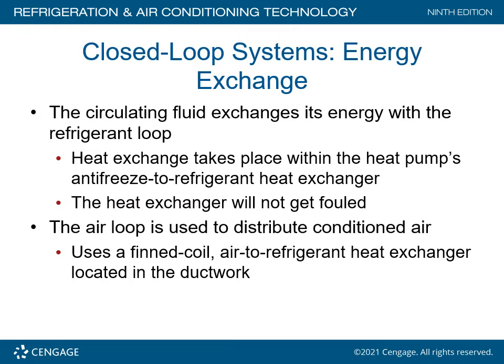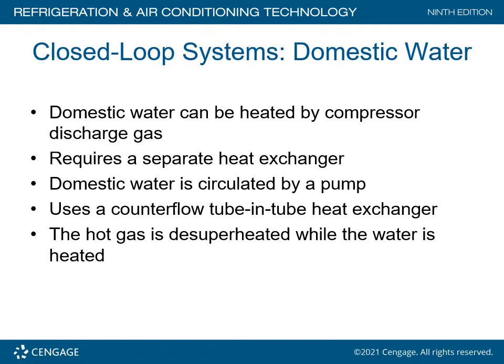In closed loop systems, energy exchange occurs when the circulating fluid exchanges energy with the refrigerant loop through an antifreeze-to-refrigerant heat exchanger inside the heat pump. The heat exchanger cannot get fouled because it uses treated water. The air loop distributes conditioned air using a fin coil air-to-refrigerant heat exchanger. Domestic water can also be heated by compressor discharge gas, requiring a separate heat exchanger with a circulating pump, utilizing a counterflow tube-within-a-tube heat exchanger. The fluids flow in opposite directions for maximum heat transfer, and the hot gas is de-superheated while the water is heated.